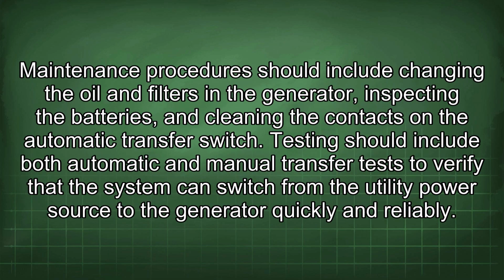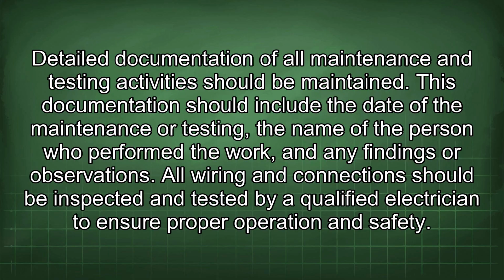Maintenance procedures should include changing the oil and filters in the generator, inspecting the batteries, and cleaning the contacts on the automatic transfer switch. Testing should include both automatic and manual transfer tests to verify that the system can switch from the utility power source to the generator quickly and reliably. Detailed documentation of all maintenance and testing activities should be maintained. This documentation should include the date of the maintenance or testing, the name of the person who performed the work, and any findings or observations.